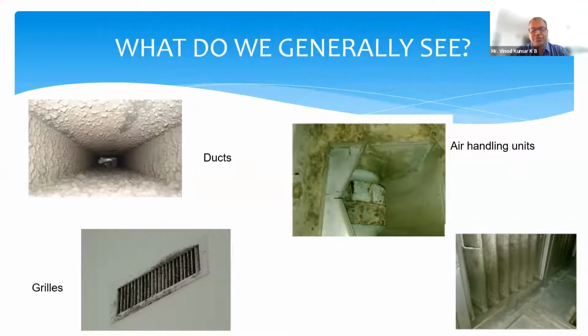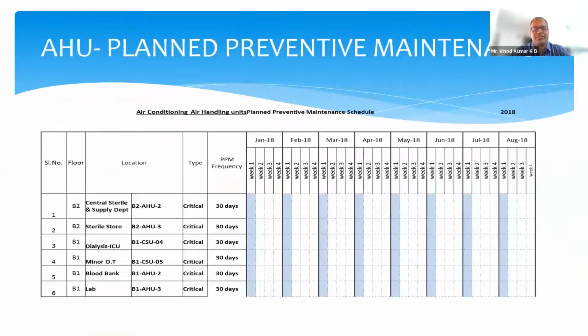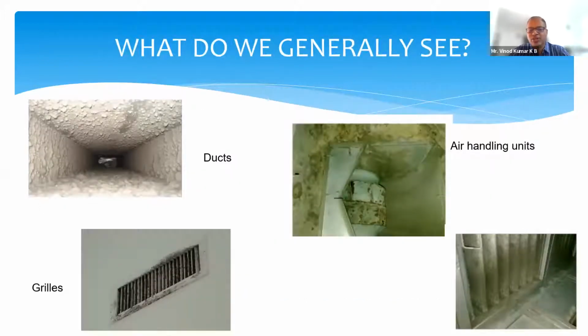So we should have a proper team to make sure that these systems are well maintained at all points of time. Now let's go into the maintenance part. We need to have planned preventive maintenance for the air handlers. And for all such critical areas like your OTs and ICUs, we need to have a PPM frequency of 30 days. Otherwise, we're going to be in trouble, because whatever you saw in the previous slide is going to happen inside your AHUs if you do not have proper preventive maintenance done at intervals of 30 days.